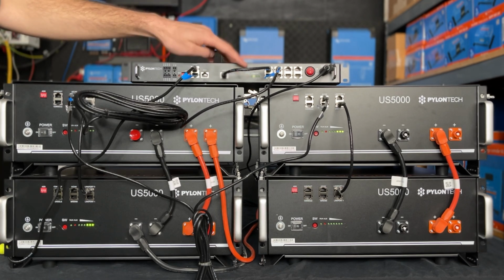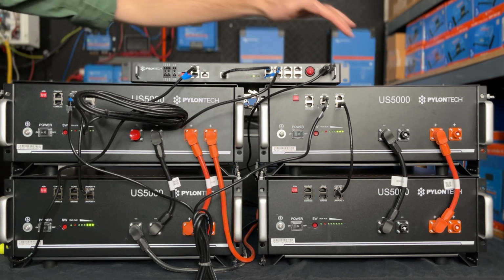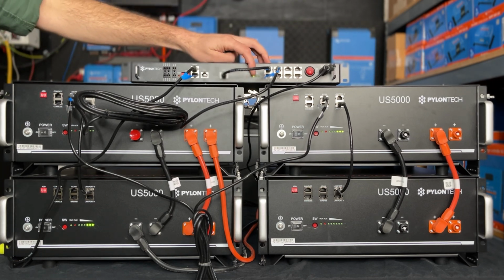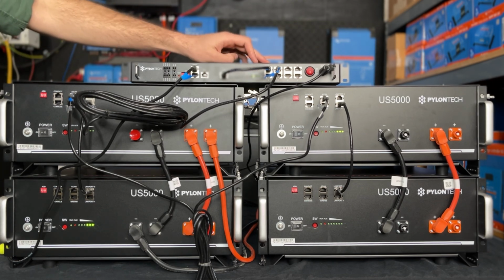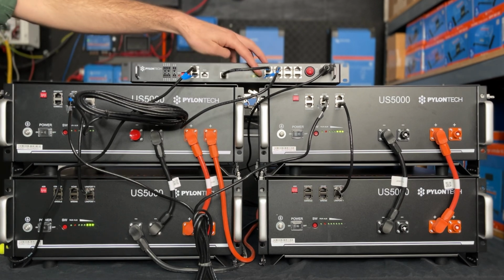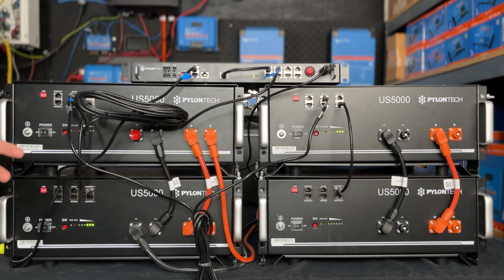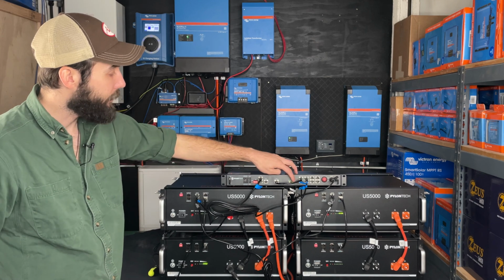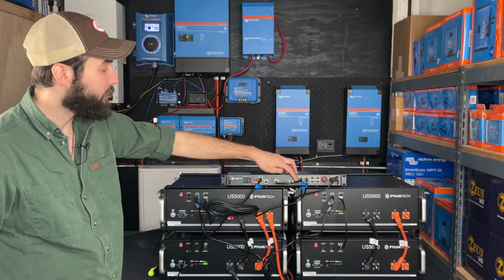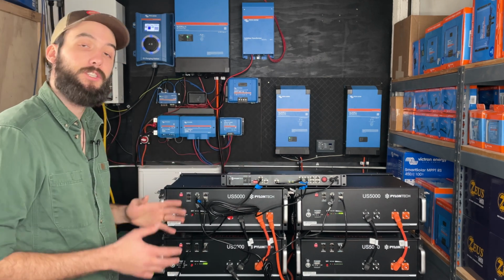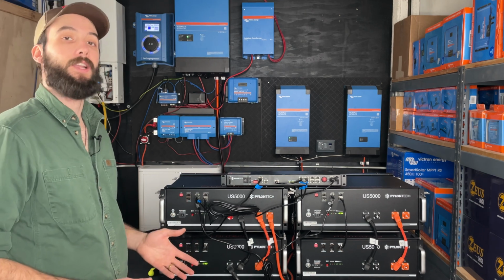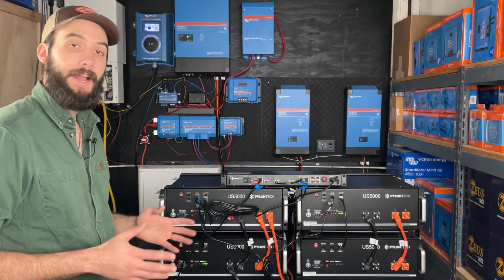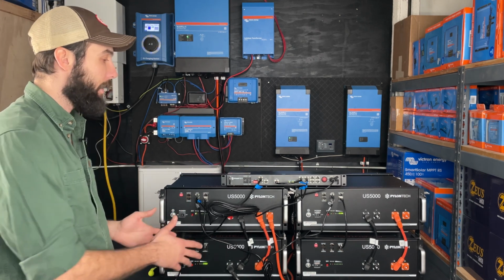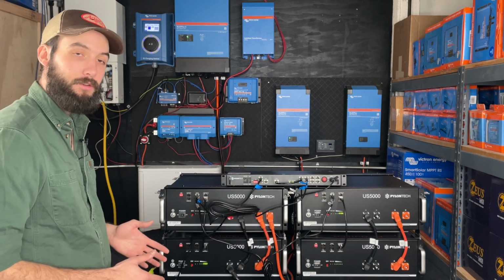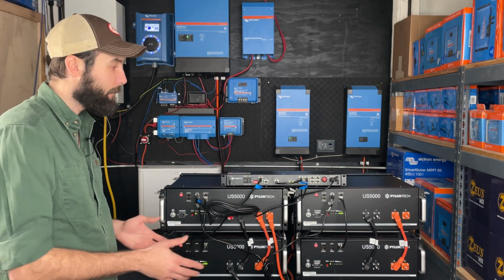Since we have 2 batteries, our indicator light is here at 2. These indicator lights are in binary form, so if I had 3 batteries hooked up, it's not going to show 2, I believe it would show 4. That's something to reference in the manual that comes with the combiner hub. That's how you make sure all your batteries are in communication and that you're actually utilizing everything in that stack.